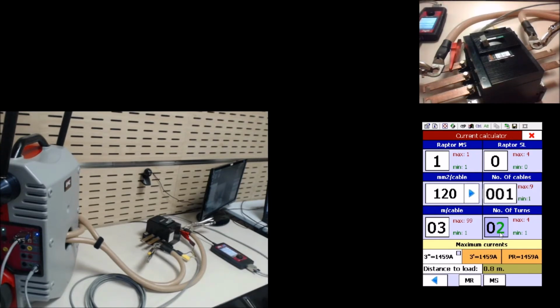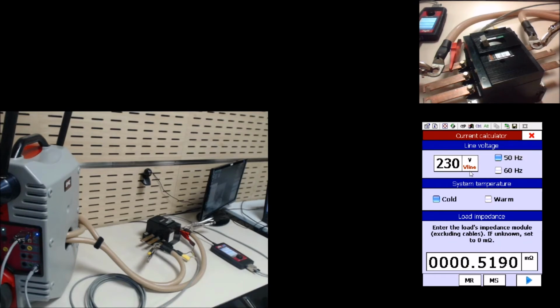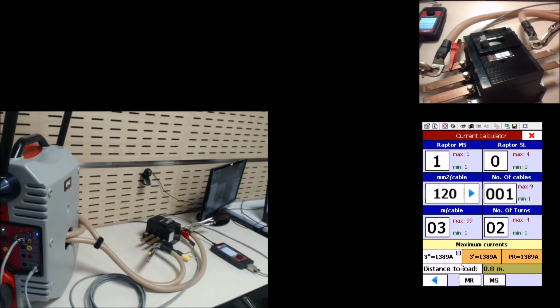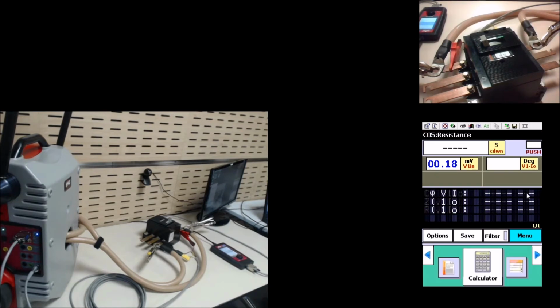So you see, according to the calculator, I am able to inject this amount of current across this pole in the circuit breaker. Okay. Of course, this is only valid if the supply voltage is steadily supplying 230 volts, as I have entered here. Okay, if my voltage input comes down to 120, I have to recalculate. Okay, this is slightly less current. Okay, so it depends on this power supply, of course, right?